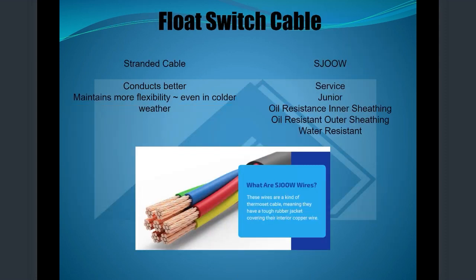And then talking about the cable, so we use SJOOW. Most of the competitors use SJOW. That's the rating of the cable itself. The extra O in there is the inner and outer jackets. So inside here on this other control switch, you can actually see there are jacketed cables inside the other cable. All of these jackets are oil resistant. So this is the better cable.